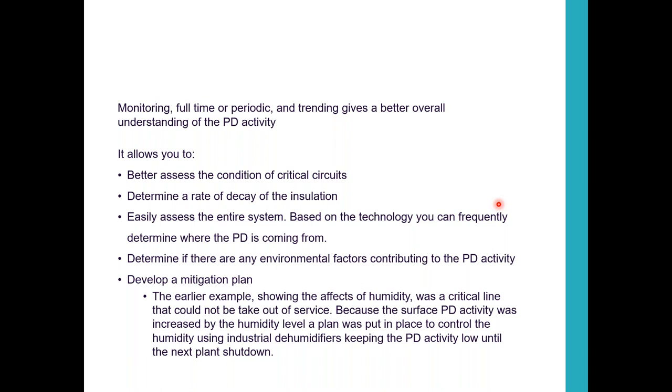It's not going to be typically a sudden, I have to take this down tomorrow and do an emergency repair. So it gives you time to plot it, trend it, monitor it, and make a mitigation plan. And that mitigation plan may be, I have to run this to failure, but I at least know what my problem is now, and I can have that equipment on hand for when it fails. Or I know I've got an outage on that area of my facility coming up in 3 months.